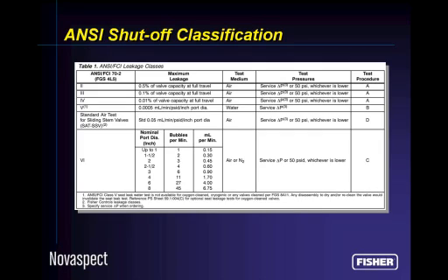In there are defined various levels of leakage classes, essentially 2 through 6. And each one of these has a particular way of testing the leakage and a particular acceptance criteria. And you can assign to your valve manufacturer the need to have a particular control valve not only control well, but also shut off to ANSI Class 4 shutoff, for example.